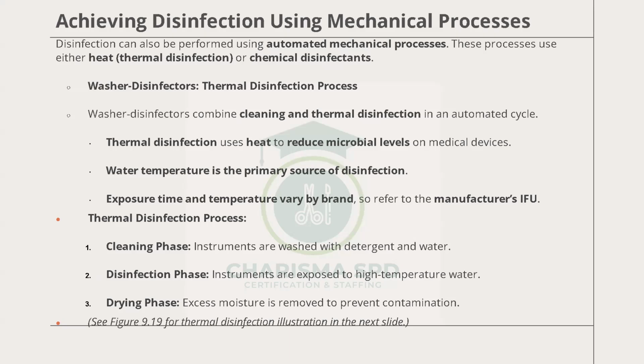To wash, this time, the water is warm, at a temperature of about 110 degrees Fahrenheit, in order to be able to activate the enzymes in the enzymatic detergent. When it is above the 110, getting to about 120, 130, 150, it deactivates.